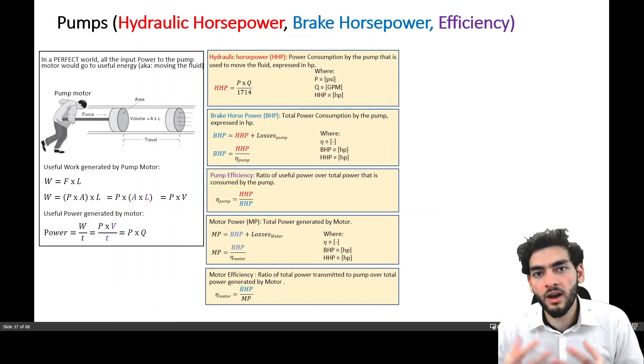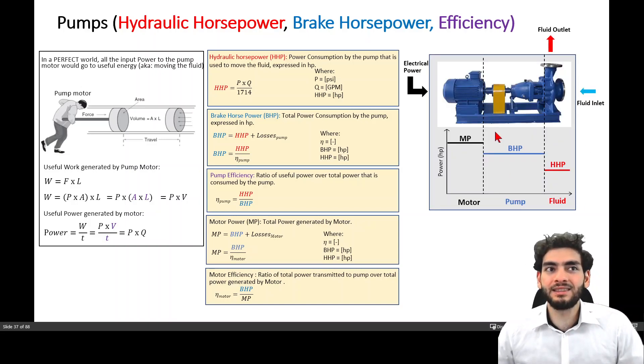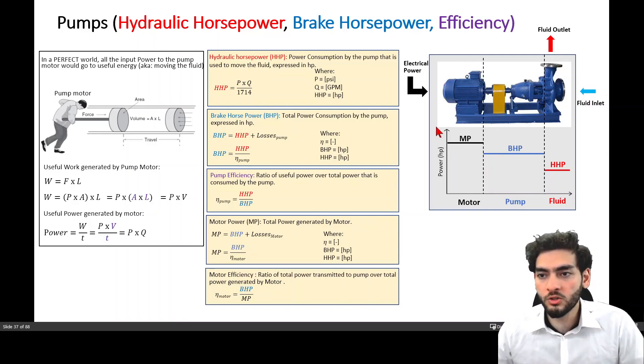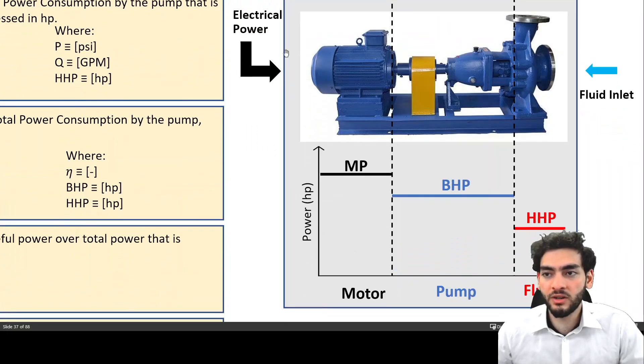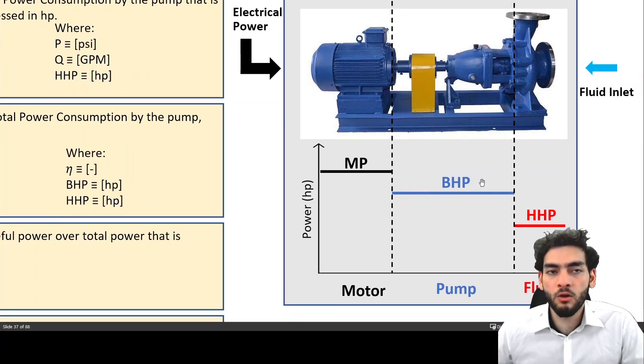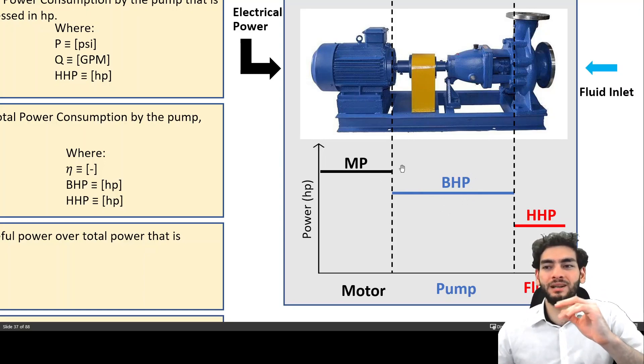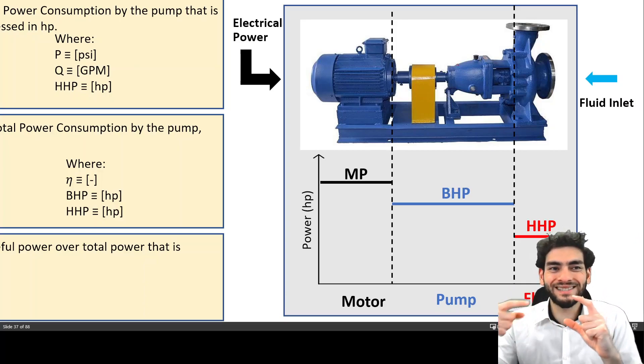These five terms are used in industry, and it is good to be aware of them even if you may not use all of them at work. This diagram is a summary of all the horsepower terms. The pump receives electrical power, which becomes motor power. Motor power transmits energy to the pump as brake horsepower, which is less than motor power due to motor inefficiencies. A portion of the energy received by the pump is then lost to pump losses.